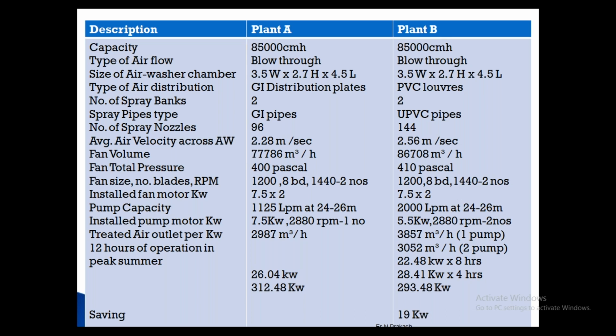As I told earlier, this is a retrofit project. In the old air distribution there was a sheet plate with holes, and 50% of the air was going through the holes. So there was a resistance for the airflow. We converted that into PVC air intake louvers, the blue color louvers I showed in the photograph, for even distribution of the air before the chamber.